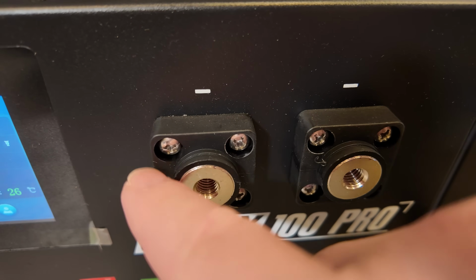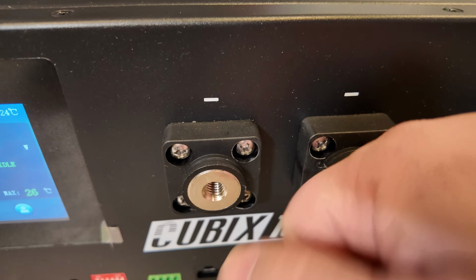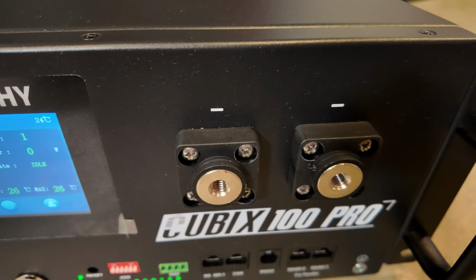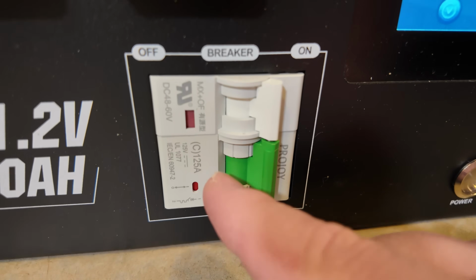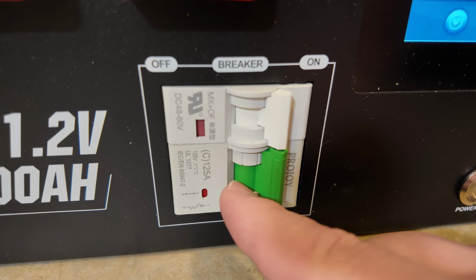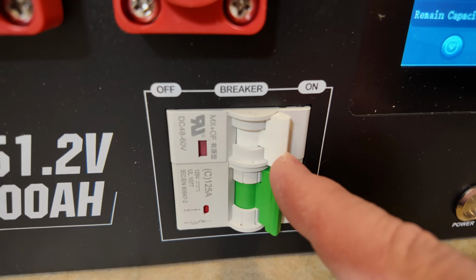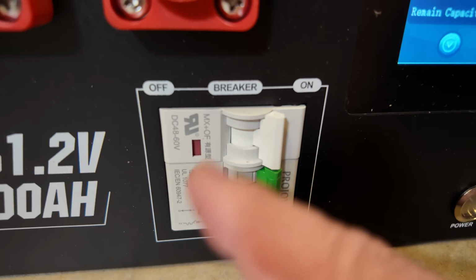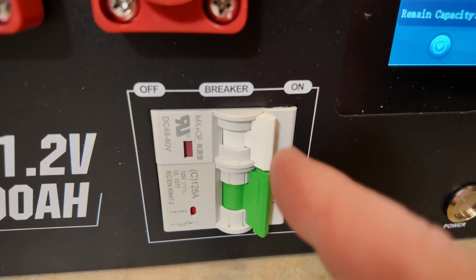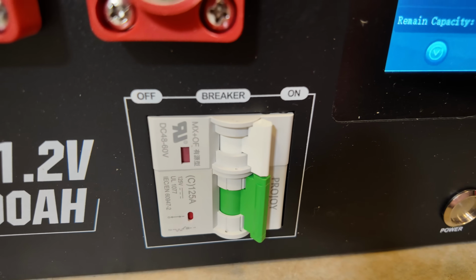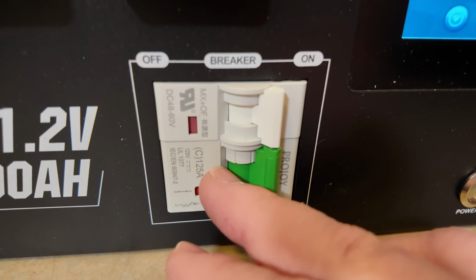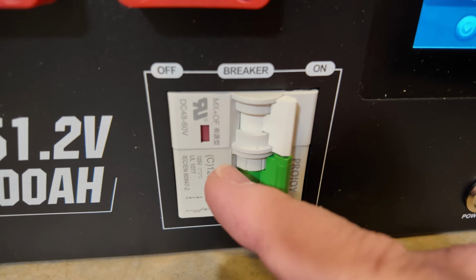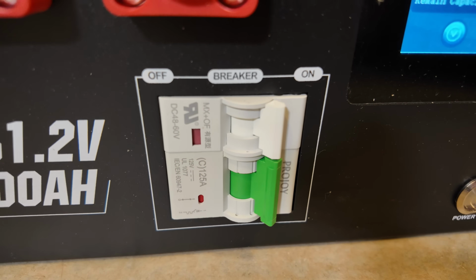Notice that the screws are recessed, so you can't short your conductor out against the screws, which is awesome. We've got a 125 amp circuit breaker right here, but it's also paired with another breaker up here, which is controlled by the BMS. So the BMS can actually flip this breaker off, even if the overcurrent threshold isn't met for the main breaker, and that's a really nice double safety feature to see.